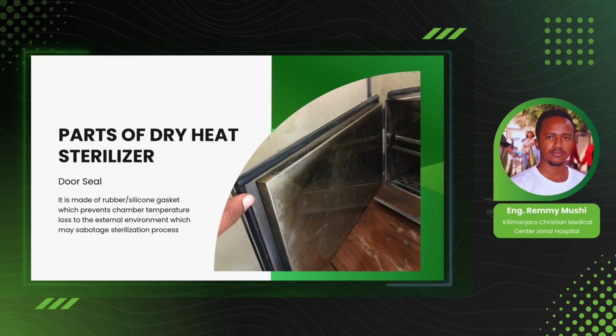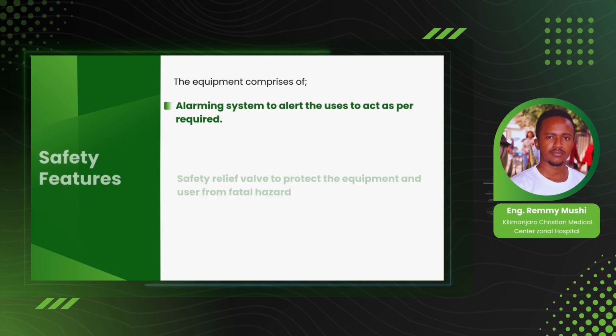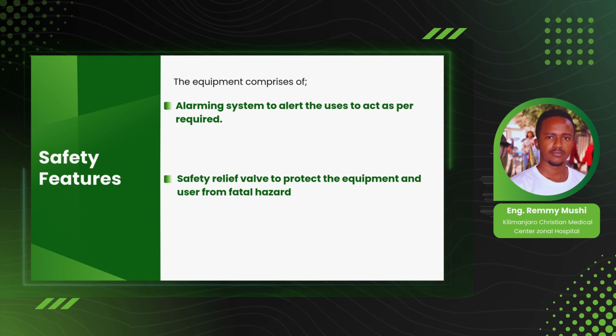The door seal is very important to ensure that there is no sabotage during the sterilization process. And the last part, or the sixth part here, is safety features. The safety features comprise the alarming system as well as the safety relief valves, in which the alarming system is used to alert the user to act as required.